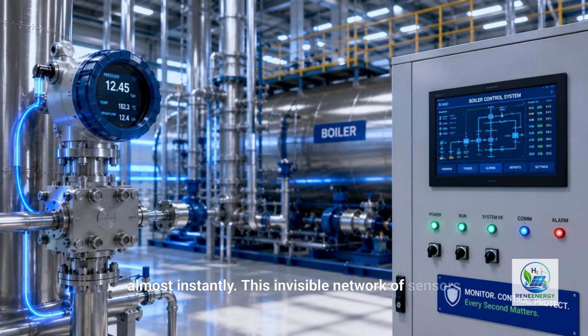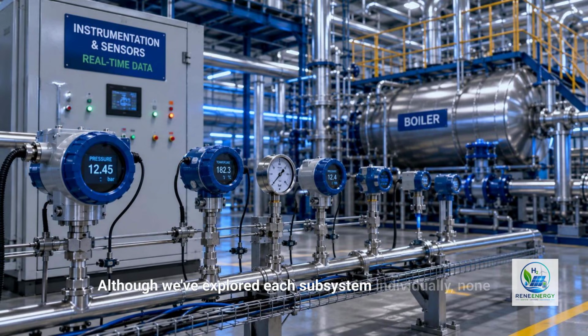This invisible network of sensors forms the nervous system of the entire boiler plant, allowing it to operate safely, efficiently, and reliably with minimal manual intervention. Although we've explored each subsystem individually, none of them operates alone. The burner, combustion chamber, heat exchanger, steam drum, condensate return, economizer, deaerator, safety systems, and instrumentation all function as one integrated machine. Every change in steam demand triggers adjustments throughout the entire plant.